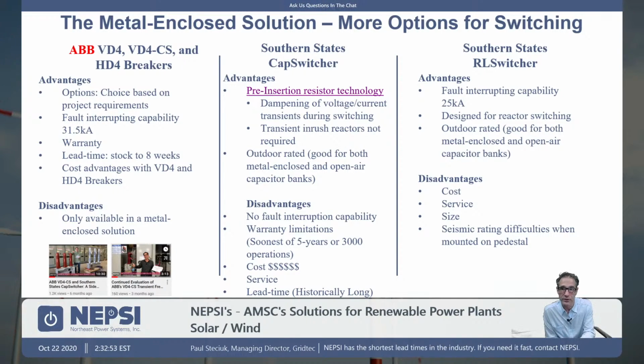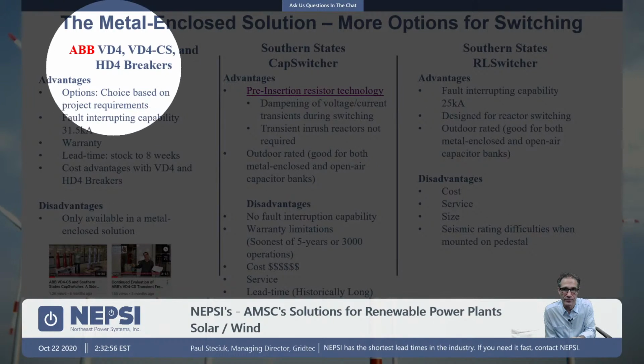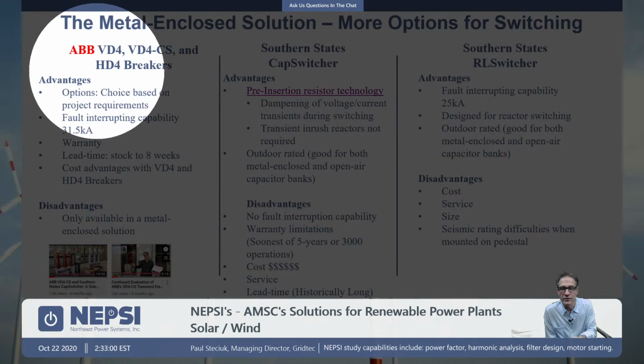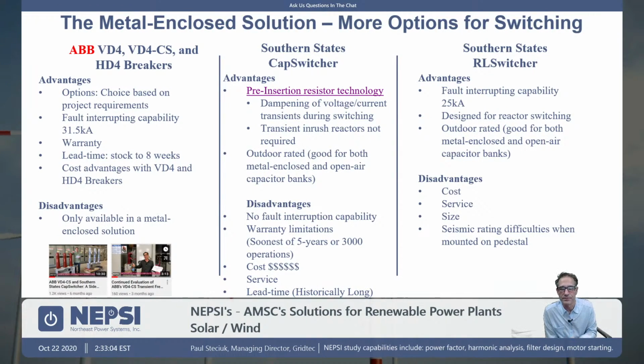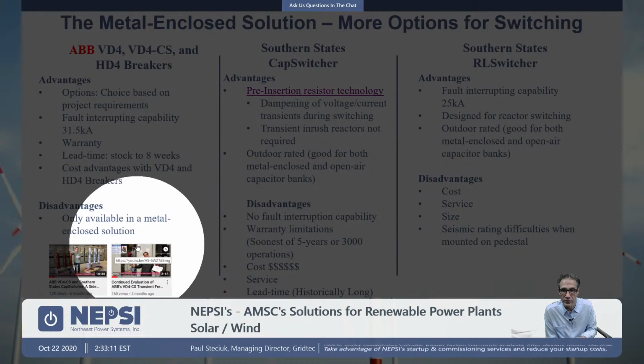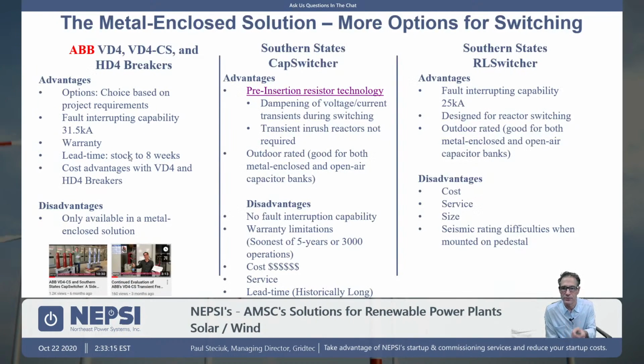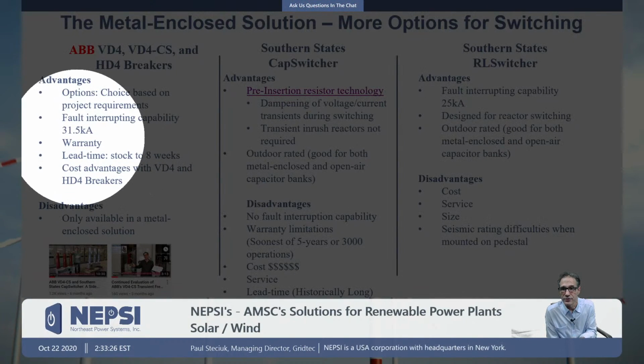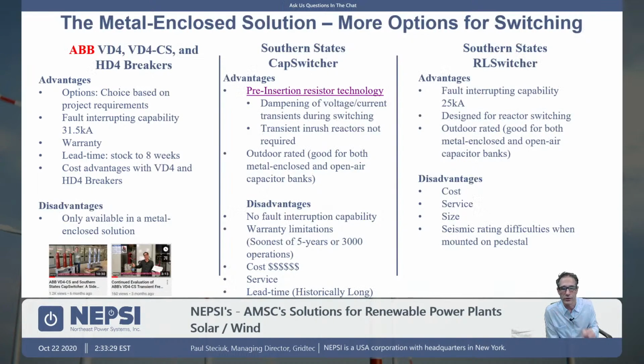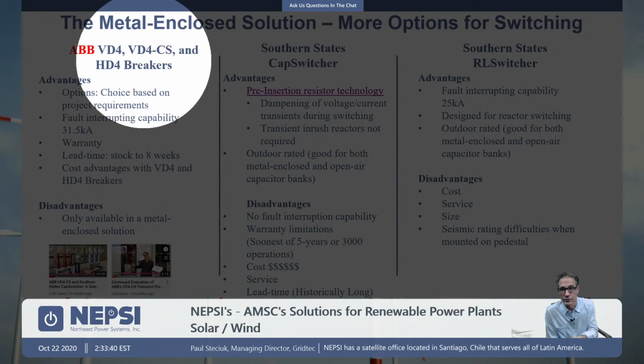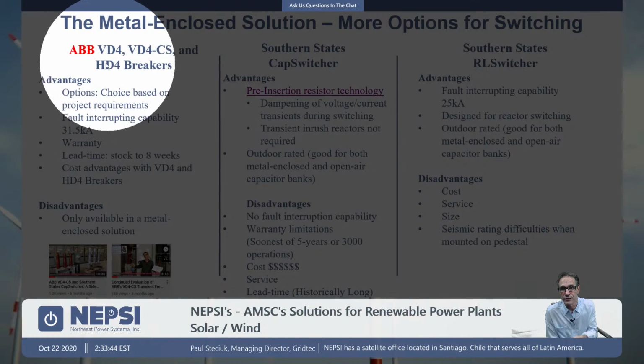So for smaller banks, we would typically use just a standard VD4, which is very price competitive. For larger banks, we would use this VD4CS, which is a new breaker out by ABB. We have 2 videos here in our playlist. If you go to our website, you can learn about that switching technology. We actually do a comparison to the Southern States cap switcher. But one of the key advantages of using a breaker is this 31.5 kA rating, is that we can eliminate the feeder breaker upstream. And then we have the RL switcher, which is another outdoor device that we would typically use for reactor switching. And the alternate switching device for that would be the HD4 here, which is an SF6 rated breaker.